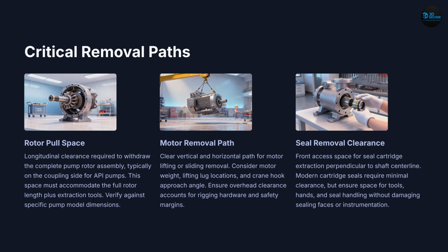Next, motor removal path. Can the motor be lifted vertically? Will piping interfere? Will structural steel block the lift? Can the crane hook approach safely? Most people never think about crane hook angles until the motor physically cannot be removed.